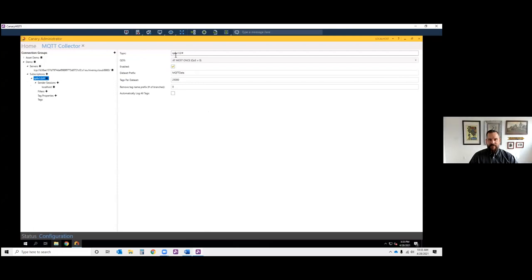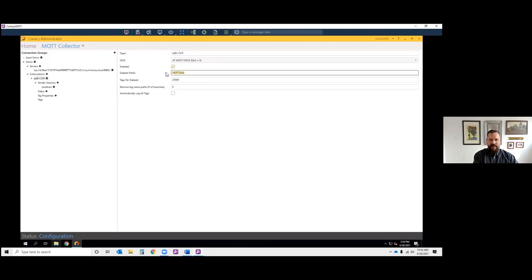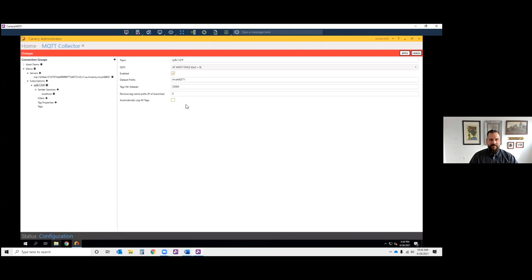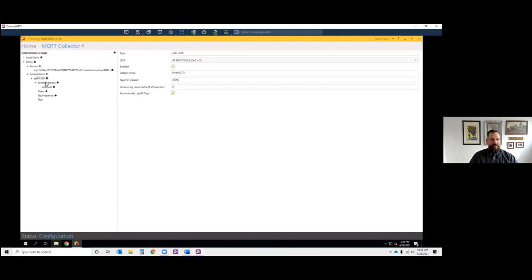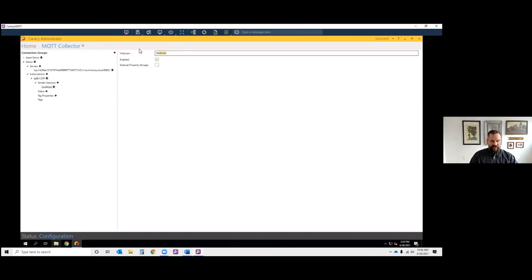With the Spark Plug specification I can watch the broker and grab everything by entering the topic 'spbv1.0/#'. If I didn't want to subscribe to everything, I could enter more detailed information including edge nodes, IDs, and come down to the tag level to subscribe to a single tag, or create multiple subscriptions to different branches of the unified namespace. For Canary's purposes I need to name the dataset — a collection of tags to log — I'll call it 'HiveMQTT1' and log all tags.